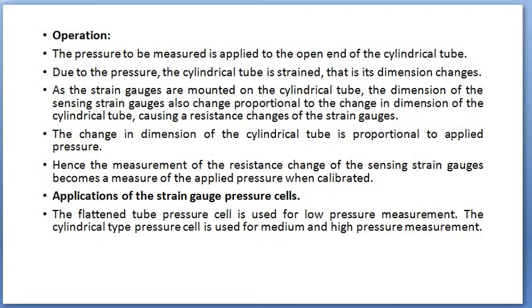So the pressure to be measured is applied to the open end of the cylindrical tube at the bottom. Due to the pressure the cylindrical tube is strained, so the overall dimension changes. It is on this tube that our strain gauges are fitted.